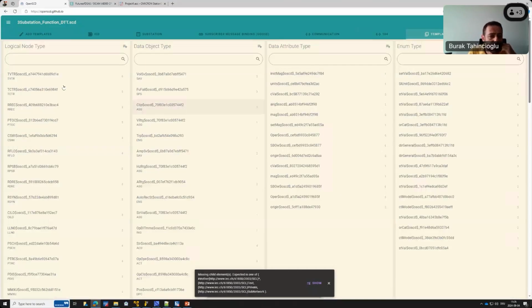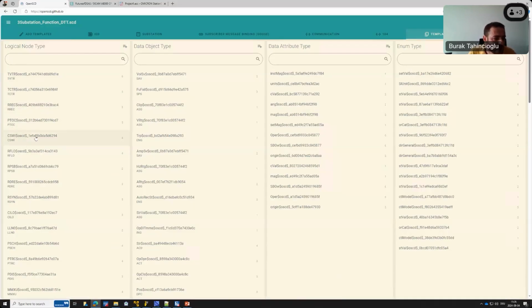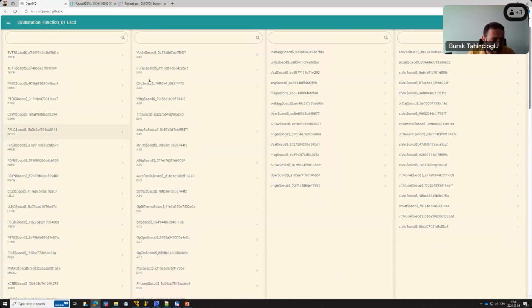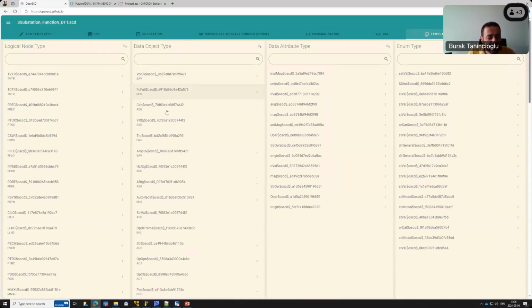I can also use this templates plugin to show our data type templates allocated in this IED. I would have the recloser, the CSWI, the fault locator, the power swing blocking as the logical nodes. And under these logical nodes, I have some mandatory, not all mandatory, but some optional data objects and data attributes.